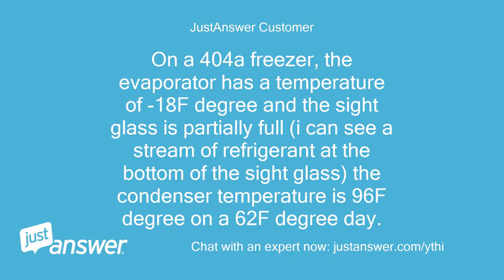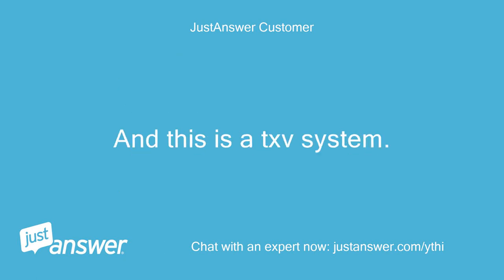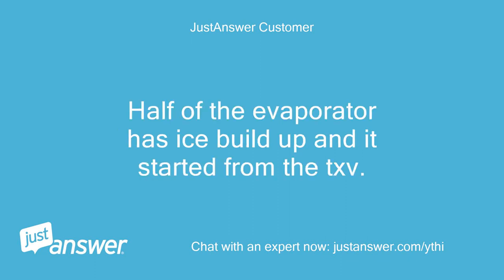On a 404A freezer, the evaporator has a temperature of -18°F and the sight glass is partially full. I can see a stream of refrigerant at the bottom of the sight glass. The condenser temperature is 96°F on a 62°F day. This is a TXV system, and half of the evaporator has ice buildup, starting from the TXV.